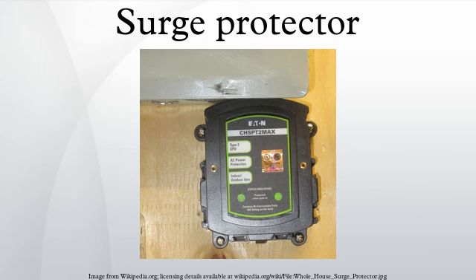Joules rating, this number defines how much energy an MOV-based surge protector can theoretically absorb in a single event, without failure. Counterintuitively, a lower number may indicate longer life expectancy if the device can divert more energy elsewhere and thus absorb less energy. In other words, a protective device offering a lower clamping voltage while diverting the same surge current will cause more of the surge energy to be dissipated elsewhere in that current's path. Better protectors exceed peak ratings of 1000 joules and 40,000 amperes.